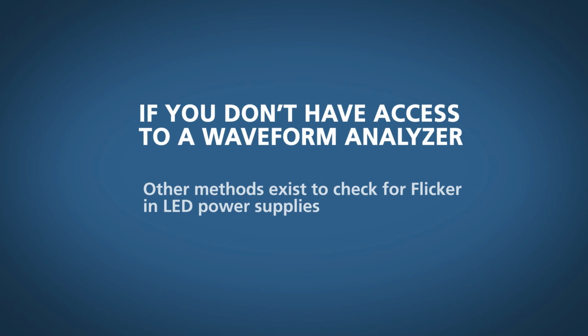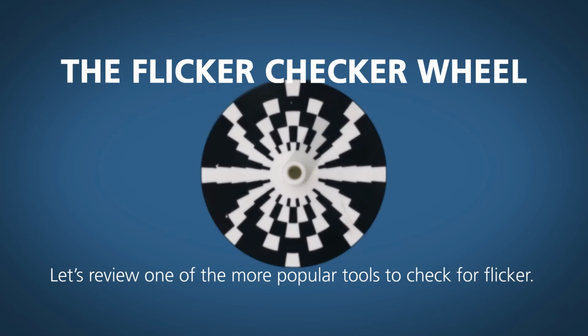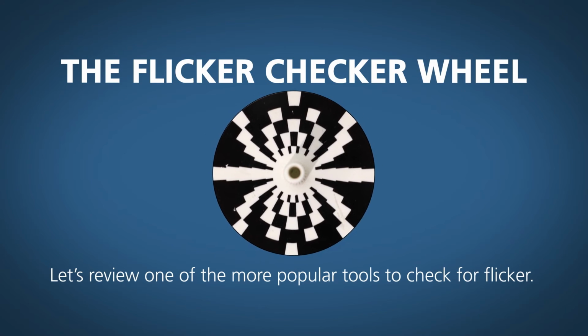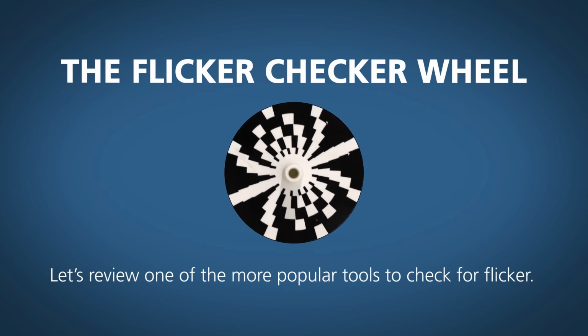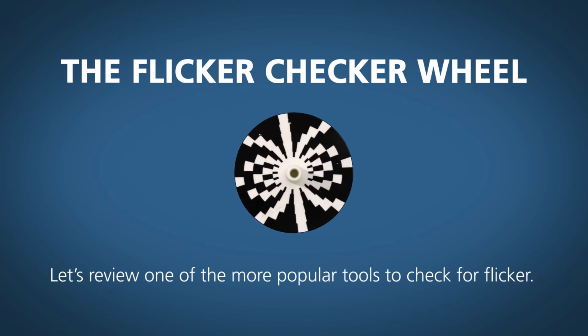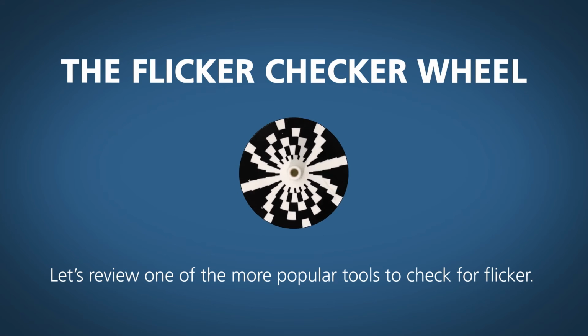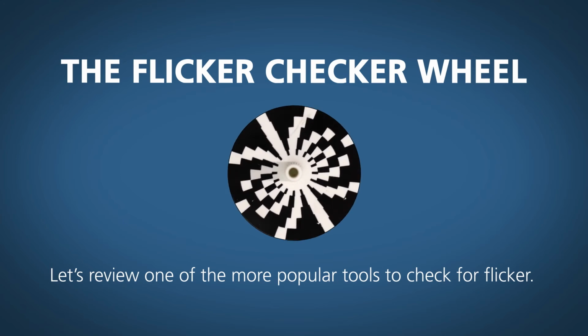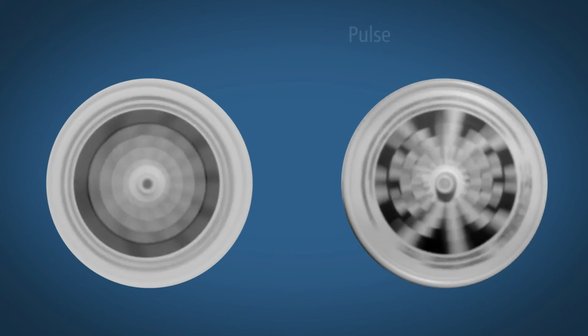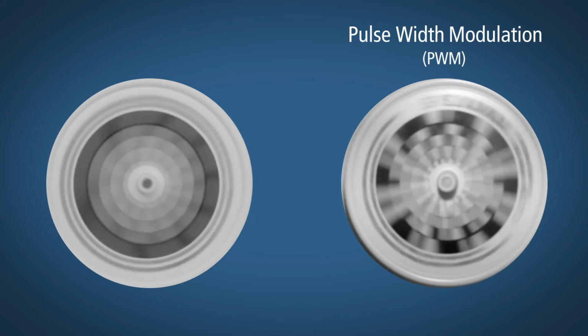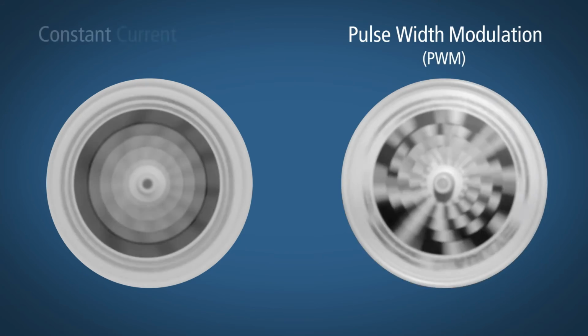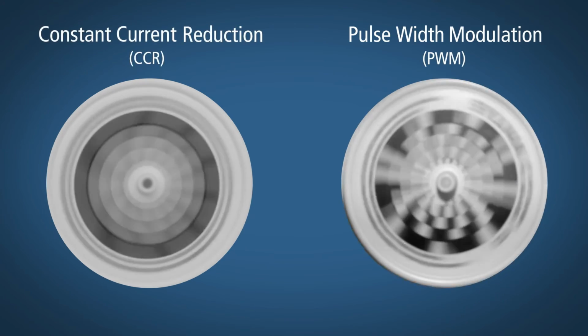If you don't have access to a waveform analyzer, a second way to check for flicker is to use a flicker checker wheel. When you spin a flicker checker wheel, the spinning pattern of light and dark shapes makes a strobe effect from the luminaire more apparent. Let's take a look at the patterns that emerge from an LED light source driven by a dimmed PWM LED supply and a dimmed CCR LED power supply.